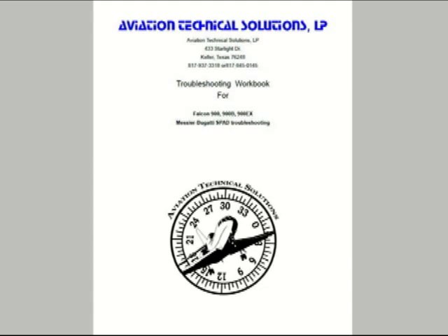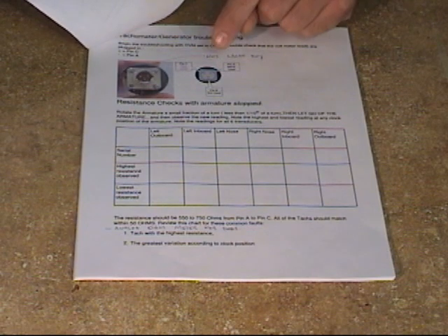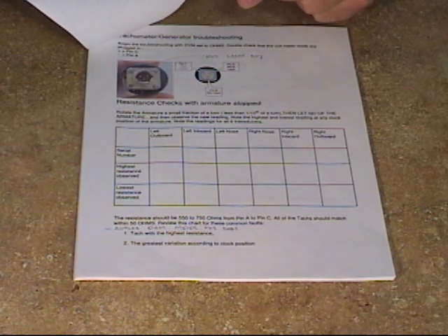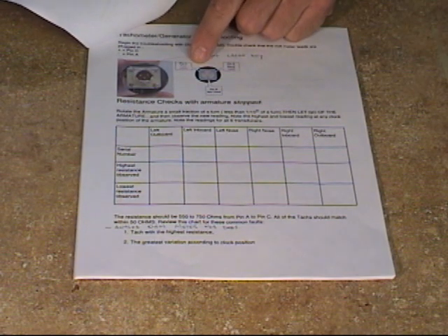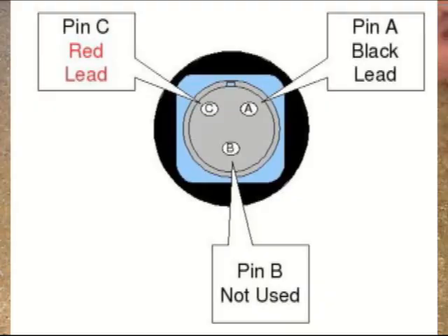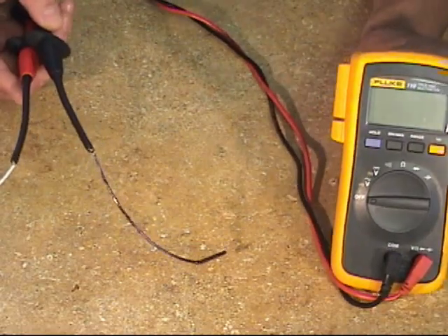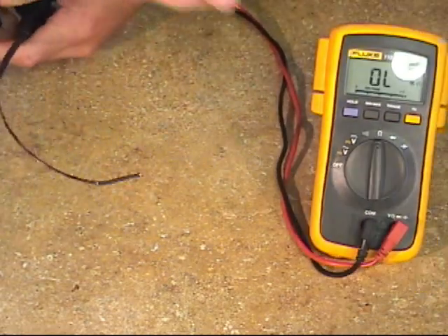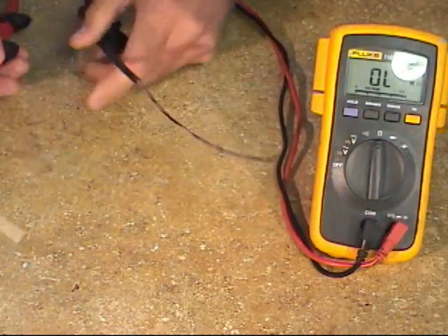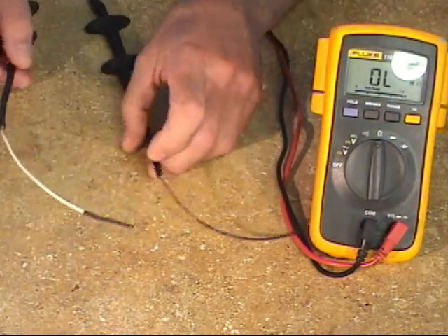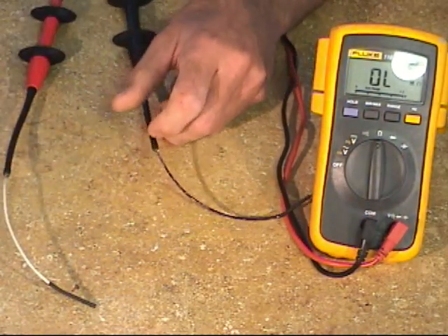There's a troubleshooting worksheet available on www.av-ts.com. We'll go right into troubleshooting the resistance on the little tach transducer. We'll pay careful attention to get the polarity correct on the voltmeter. It will become important as we move along, the polarity that we use on the tach, so on the meter. So we'll make sure we're, for example, red lead plugged into positive, goes to a red lead, goes to a white test lead, whatever, so you can keep your polarity straight.